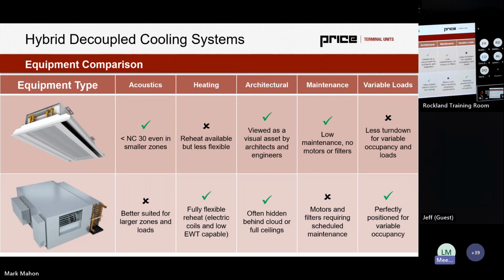Architecturally, the chilled beam is really viewed as a visual asset by a lot of architects and engineers and building owners. So that can be a huge asset. But in some cases, an owner might want products hidden behind ceilings. I would say generally architecturally driven projects often lean more towards the chilled beam, but the flexibility of a fan-powered terminal, potentially with perimeter slots or cloud or open ceilings. We're seeing a lot of open ceilings with more industrialized looking equipment that gets painted. That's popular. So there's an option there.